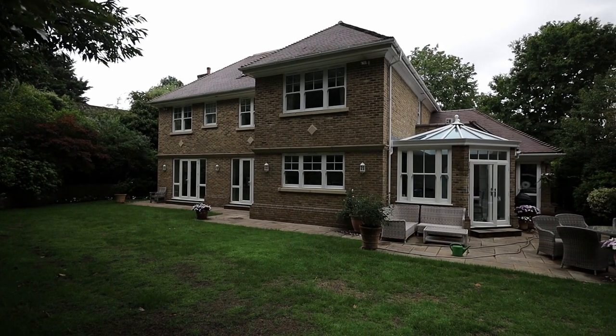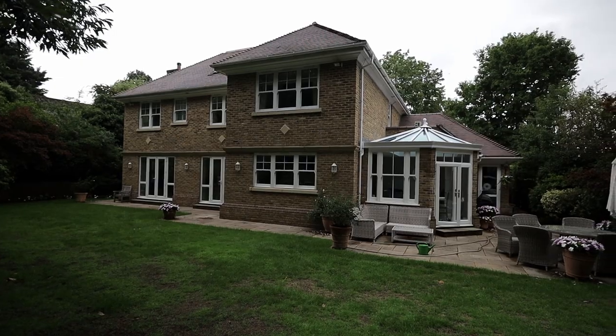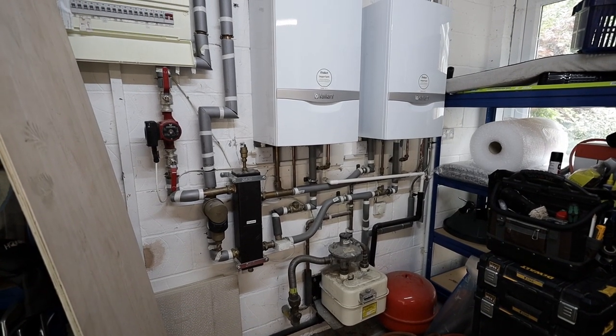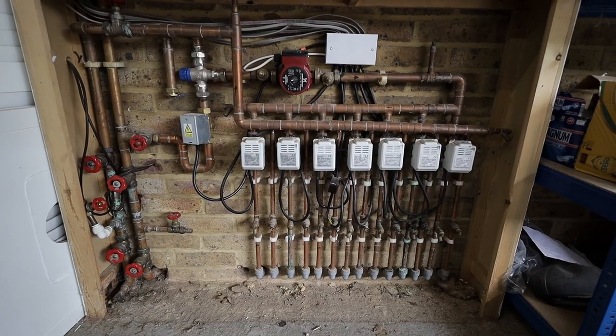Hi, Simon from Urban Timers here. In this video I'm going to take you through a full process of energy efficiency improvement to a central heating and hot water system in this 4,000 square foot property. At the moment the energy consumption is around 50,000 kilowatt hours per year. I've calculated the heat loss and energy consumption, and it should be well below 40,000 kilowatt hours for both heating and hot water.